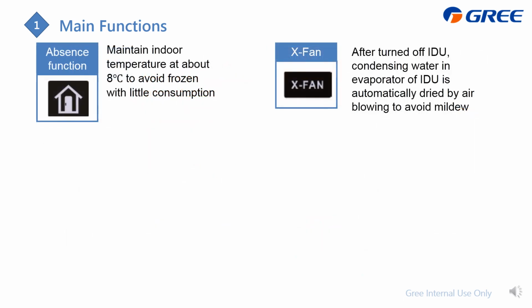Absence function, also called 8-degree heating function. This can maintain your indoor room temperature at about 8 degrees to avoid freezing. X-fan: when you turn off the indoor unit in cooling, the indoor fan still operates for another 2 or 3 minutes to blow out the condensing water to avoid moisture.